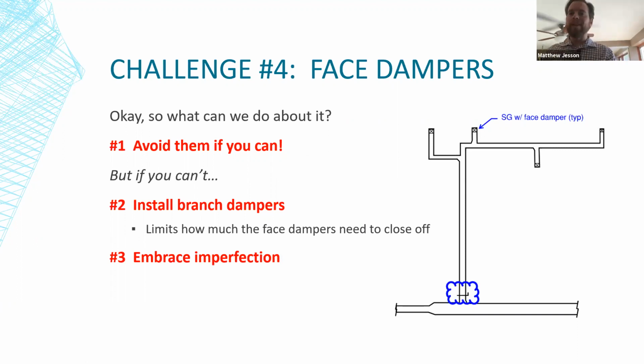And finally, you can kind of just embrace the fact that they're not going to be perfect. Maybe it's something that you can just live with in this particular situation. If you've got an open area where all the airflow is getting to the room, but with face dampers, it's just very difficult and sometimes not possible to get those outlet airflows to design. There are going to be some that are fully closed and still over design, and some that are fully open and still under. And that might just be how things turn out if you have to rely on face dampers. Just trying to be realistic with that.